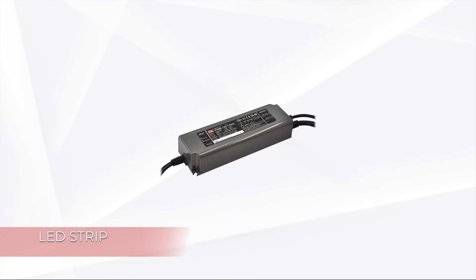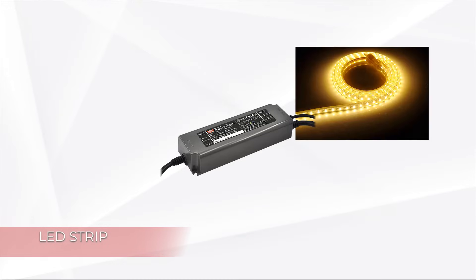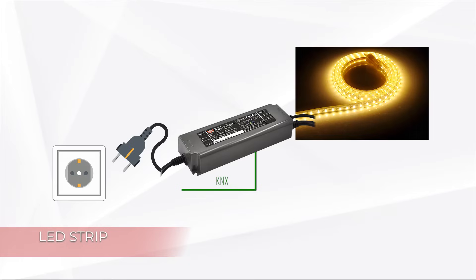After ETS programming, the driver is placed at its final location and the LED strip is connected to the output of the driver. Then the KNX cable is connected for telegram commissioning, followed by connection to 230 volts AC mains voltage. When the driver receives a command from a push button or any other KNX input device, the light is controlled to turn on, off, or dimming.